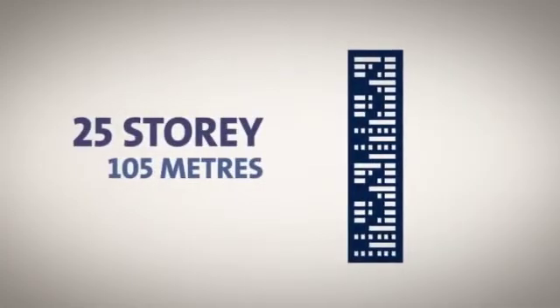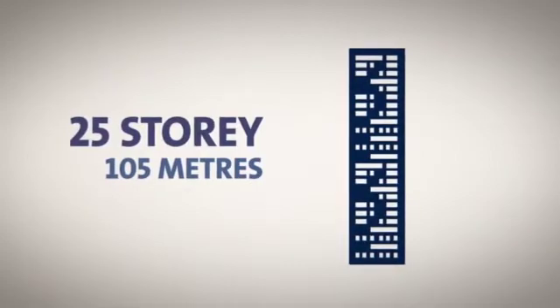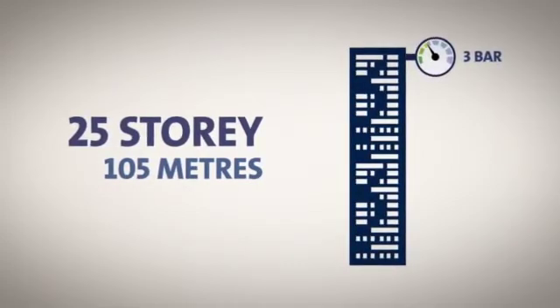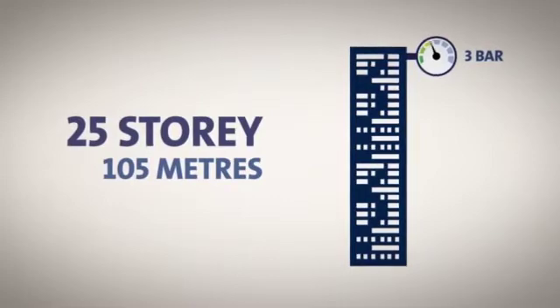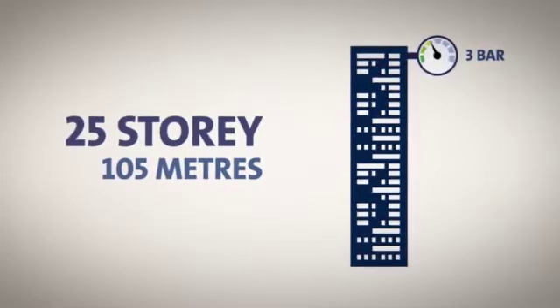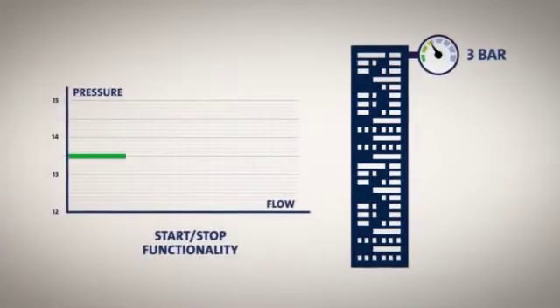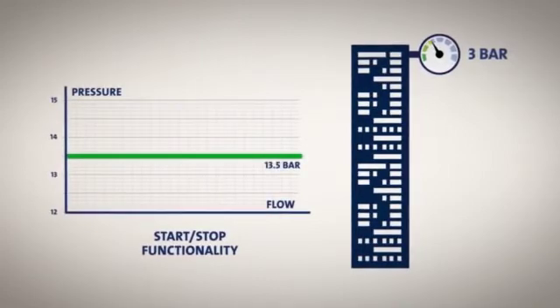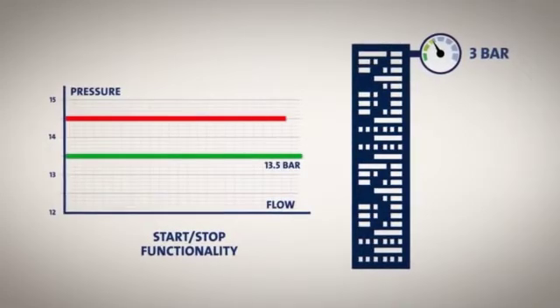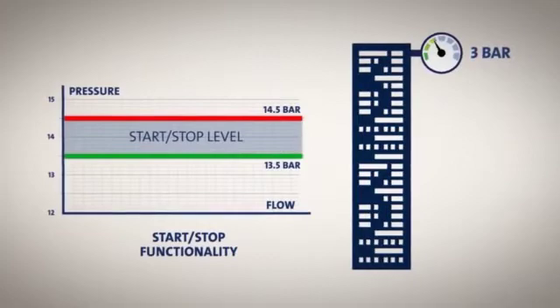Let's take a 25-storey building, equal to 105 meters, as an example. Say you need the minimum pressure on the top floor to be 3 bar, equal to 30 meter water column. The start level must then be at least 13.5 bar and the stop level approximately 14.5 bar.